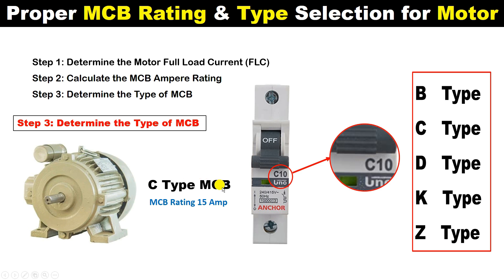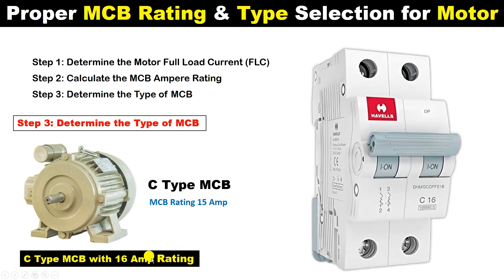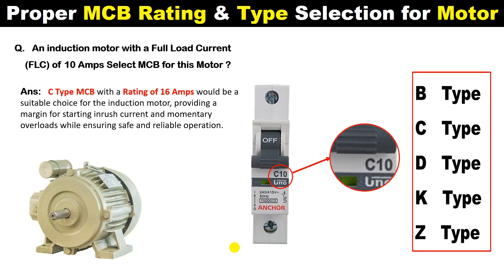So now we know that we have to use a C type MCB and the rating will be 15 ampere. However, if you go to the market to buy an MCB, you won't find a 15 ampere MCB — you have to buy one of more than 15 ampere. You can find a 16 ampere MCB in the market. So the MCB you must use will be C type with a current rating of 16 ampere. I hope you understood how to do the selection of an MCB for a motor.